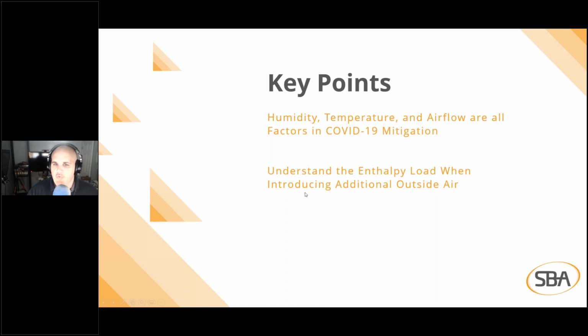Understanding the enthalpy load when introducing additional outside air is critical, because the last thing you want to do is start to highly saturate the inside of your building, and it's going to be a really difficult problem to overcome once you've built up that enthalpy load. It's kind of like how I tell my wife, hey, let's turn off the air during the day when no one's in the house. I'm like, that's a horrible idea because it's going to get so humid in the house. It's not going to be hot, it's just going to be humid, and it's going to take a lot more effort to remove that humidity than to just keep the house a little bit cooler during the day. And air changes can be used in lieu of outside air in some cases.